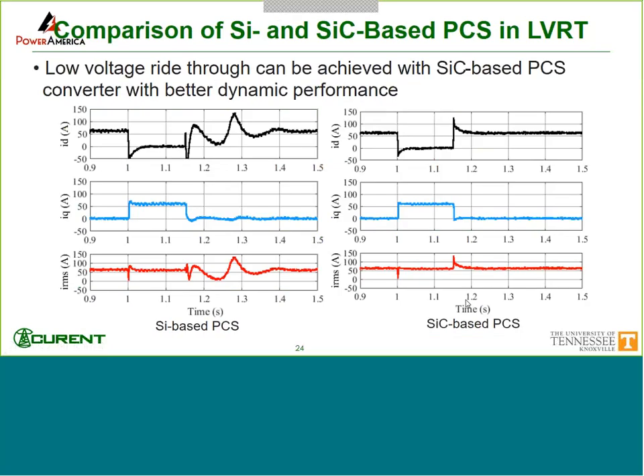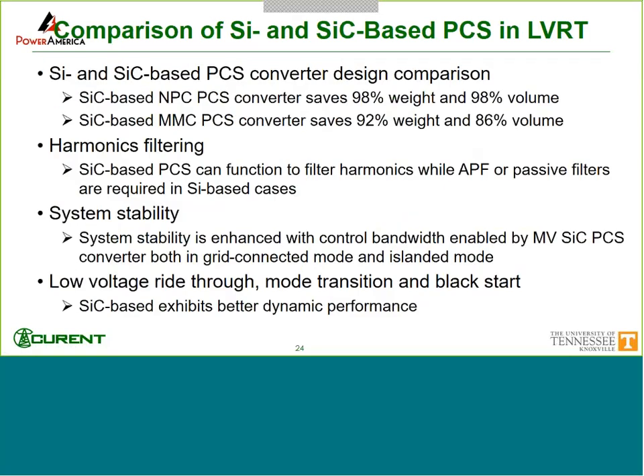So the low voltage ride-through, I actually already showed this earlier, and this is the silicon-based case and the silicon carbide-based case. They both can ride through on the grid side, but there is a little bit better dynamic performance. Of course, on the microgrid side, it's much better because the voltage can be maintained.